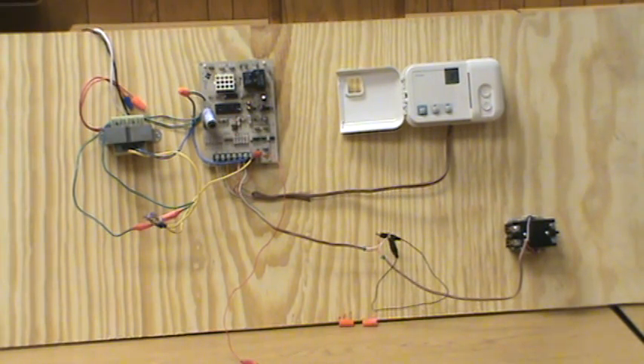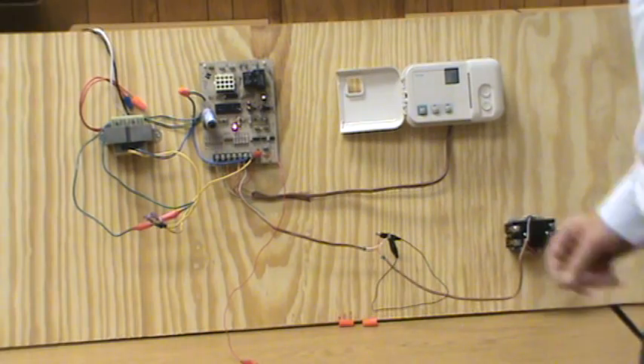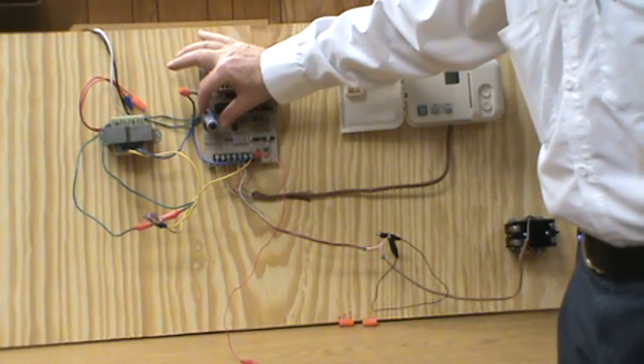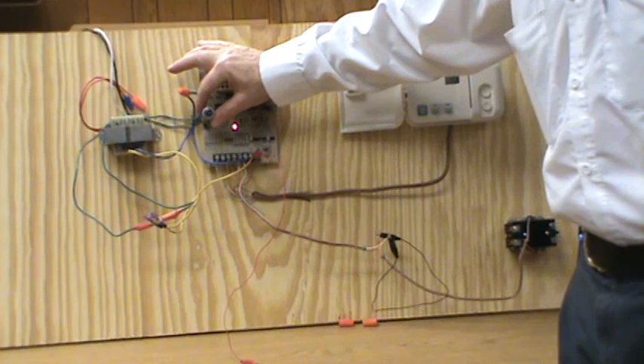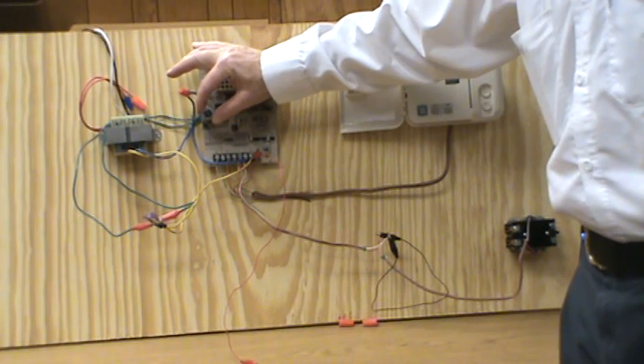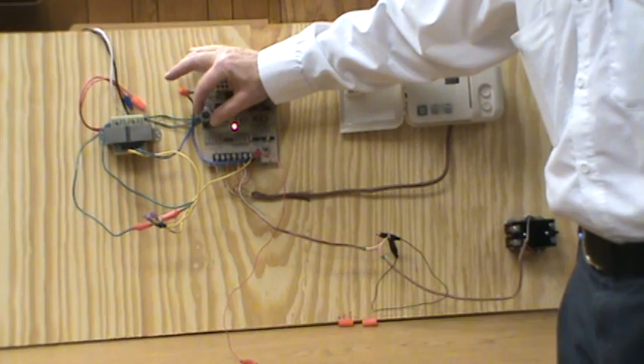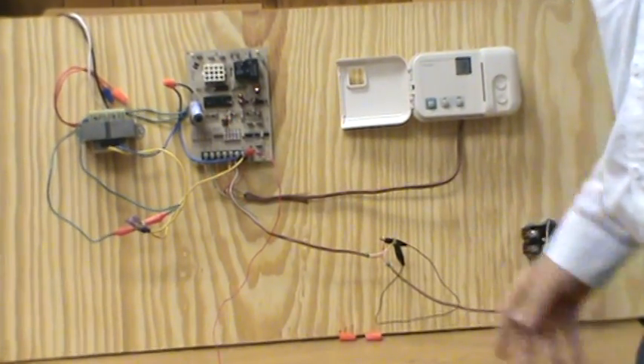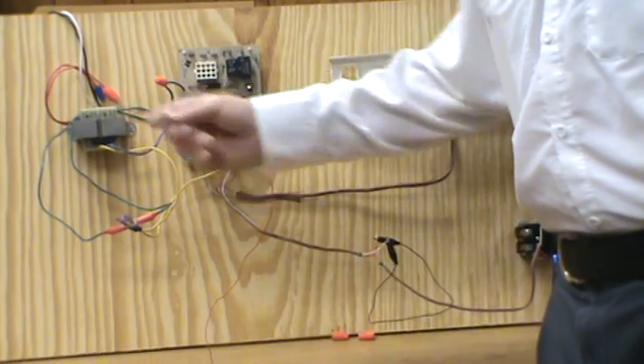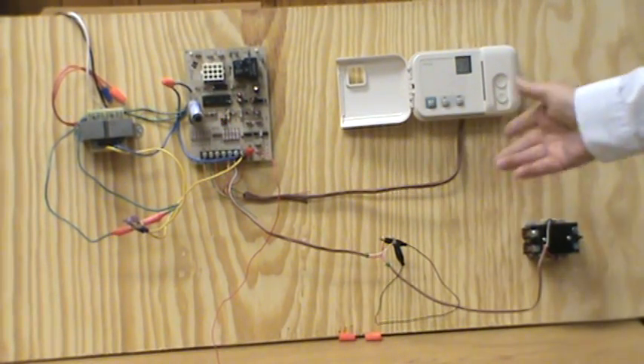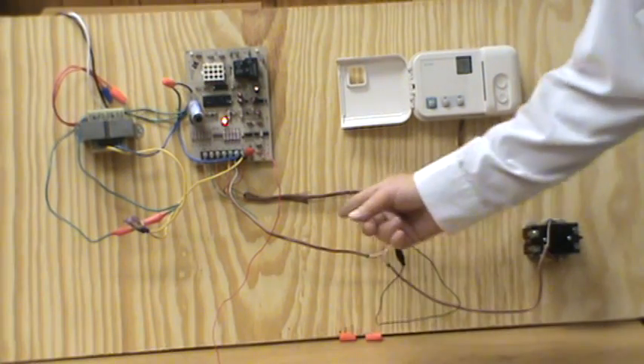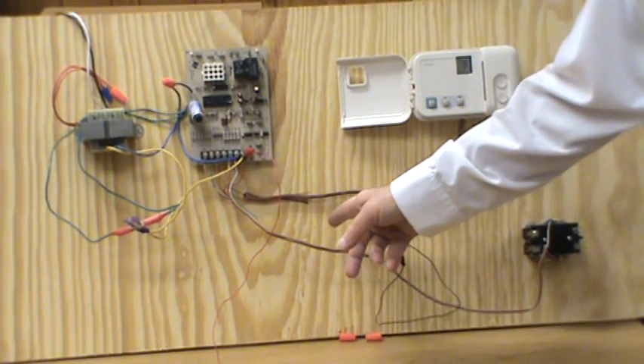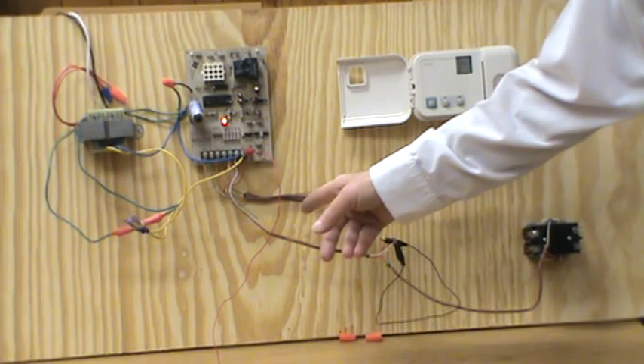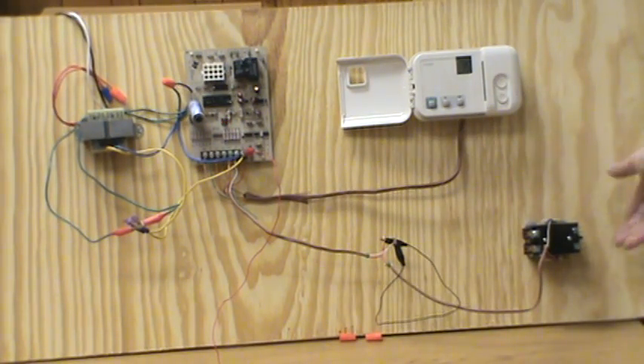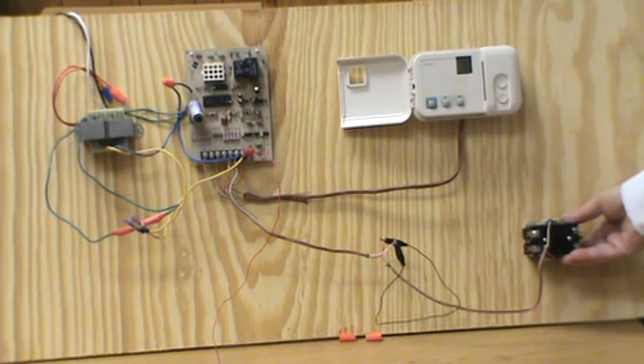Okay, we're back. And what I've done here, I went ahead and clipped the Short Pro tool right over here so we can easily see this LED that's going to light up if we catch a short. And we got a typical 40 VA transformer on a residential system, circuit board, thermostat, and this little stretch of wire, we're going to pretend this is the wiring going through the attic to the outdoor unit, and we have a contactor off to the side over here which is representing the condensing unit contactor.